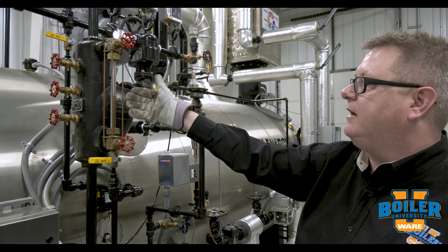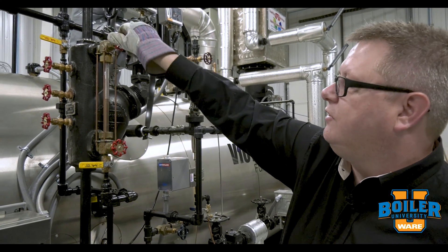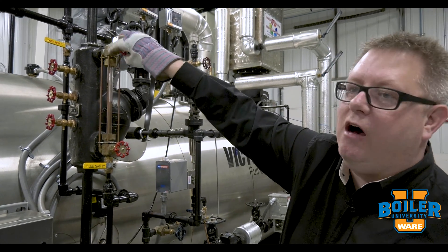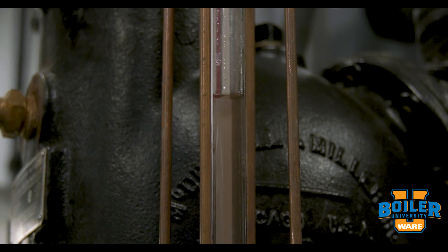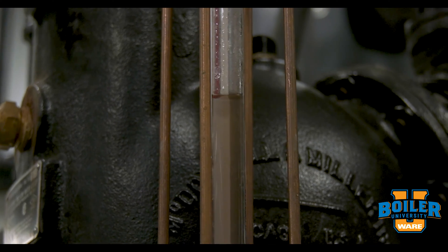If that happens when we blow down the sight glass, the best thing to do is just slightly turn that valve in, and that will dislodge that ball check and will allow the sight glass to return to its normal level.